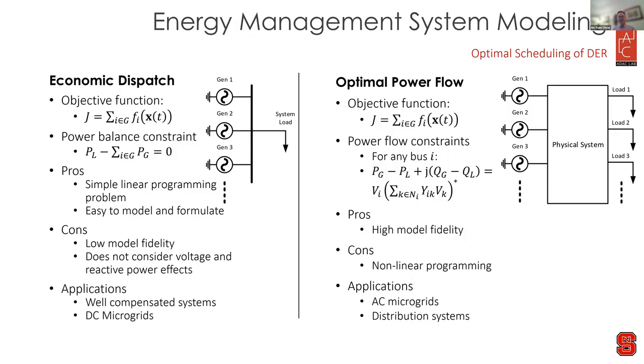In economic dispatch, power system network details such as power lines and topology are not modeled. It assumes a common bus connection for all generators and demand. The pros is that a simple linear programming problem can solve it, easy to model and formulate. However, the disadvantage is that the model has low fidelity and does not consider voltage and reactive power effects. So usually we use this for well-compensated systems or for DC microgrids.